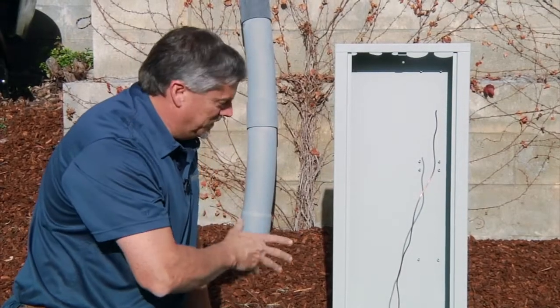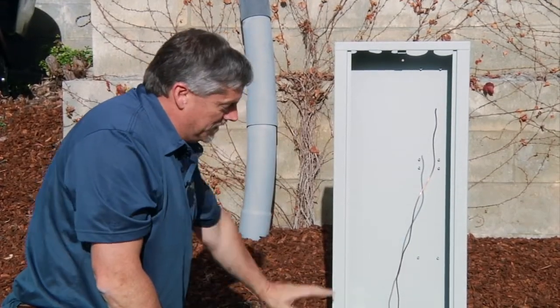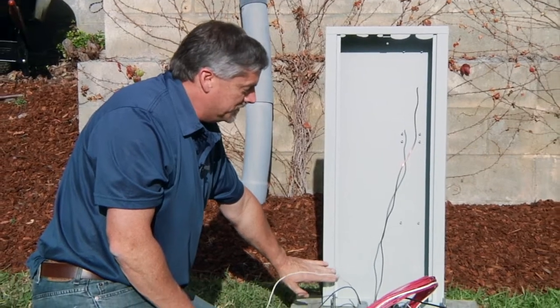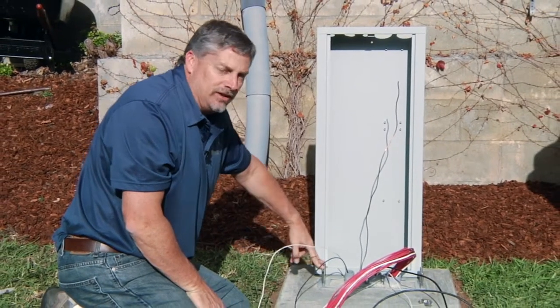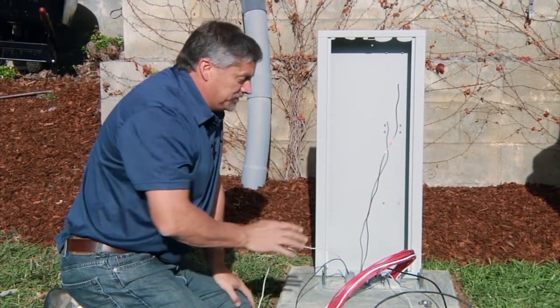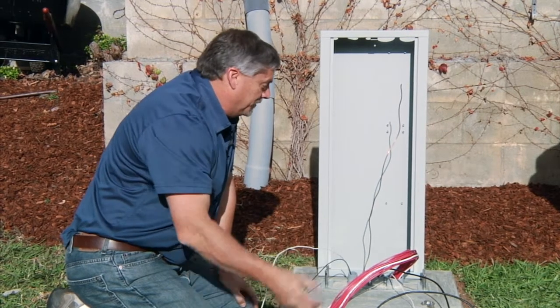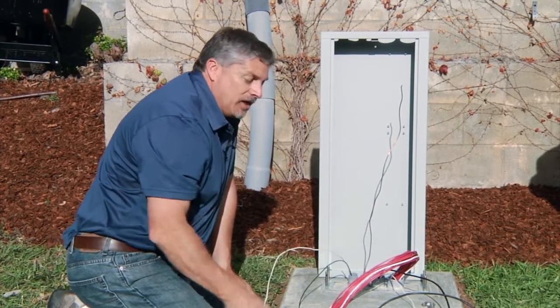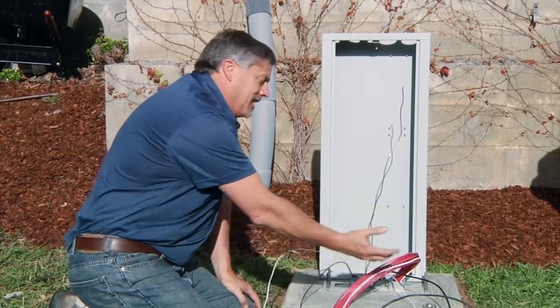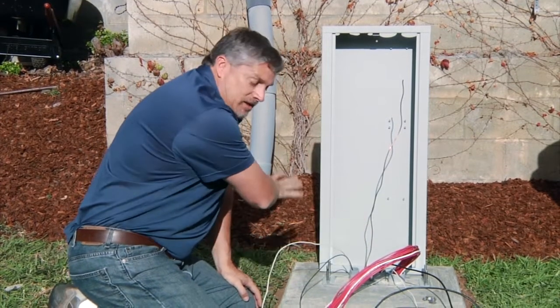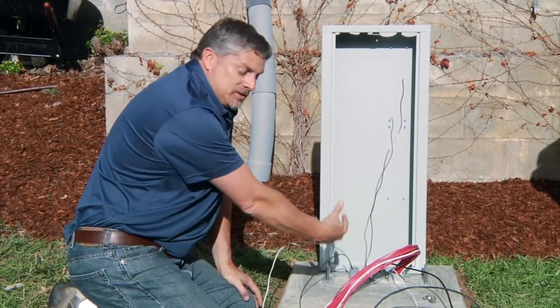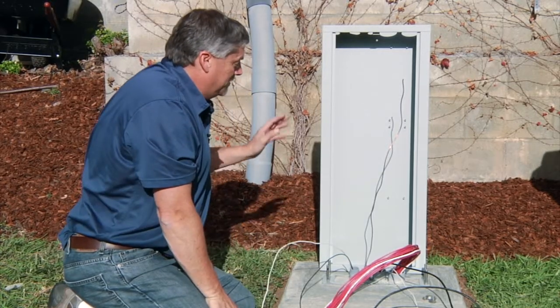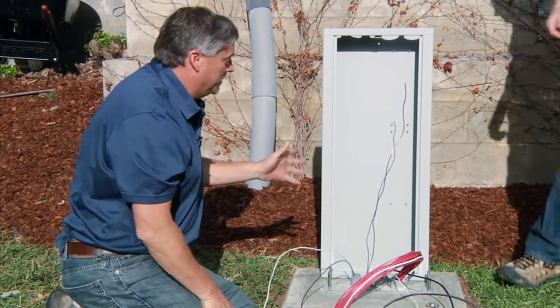So the next step we'll be doing here is to install the lower 4 holes of the metal pedestal over onto the 4 anchors. But you'll notice first I've pulled all the wire through from the conduit in the field coming up and out. You'll want to do that first because it makes life a lot easier to get those wires pulled up with no pedestal in place. But now that my wires are all pulled up, we'll go ahead and put the pedestal on, and you might need the assistance of a helper to do this.